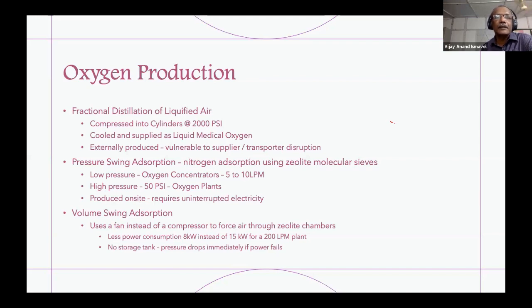The second method is pressure swing adsorption. This uses pressure to pressurize air, pass it through a dehumidifier, and then through molecular sieves which absorb the nitrogen, about 78% of air. Once you do that three or four times, you reach 90% concentration, which is supplied at a minimum of 50 psi into the main pipeline.